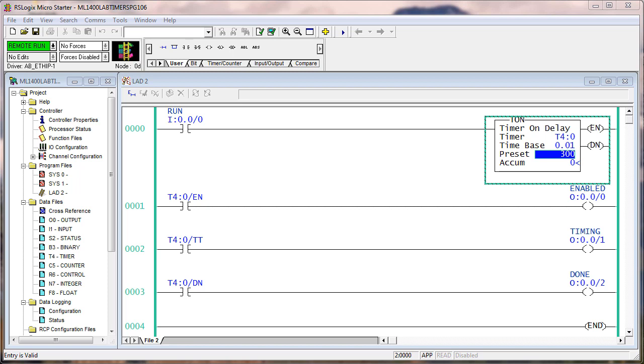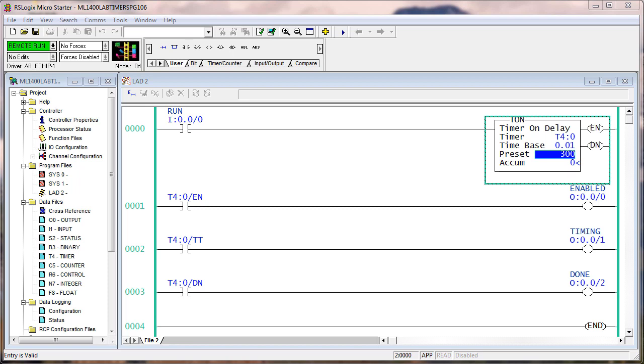When I turn this on, the enable and the timer timing bits are going to go on right away. Watch the logic. If the rung goes false, it completely resets — so it doesn't have to time out to be reset. If you watch, the enable and timer timing bits are on at the same time. And when it's done timing, the enable stays on and now the done bit is on. It's that simple.